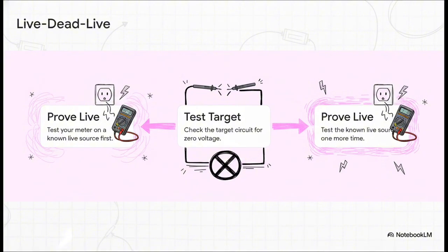source. Step 2, you test the target circuit you are about to work on. This is where you expect to see 0 volts. But wait, you don't stop there. Step 3, you go back and test that known live source one more time. This proves that your zero reading actually means the circuit is safe, and not just that your meter leads broke or a fuse blew inside your tester during the second step. It's the only way to be absolutely certain you're not about to touch a live wire.